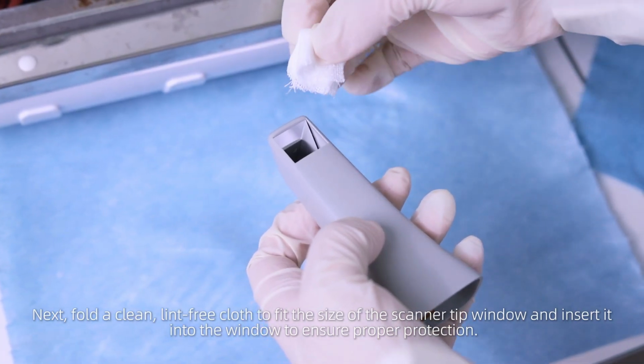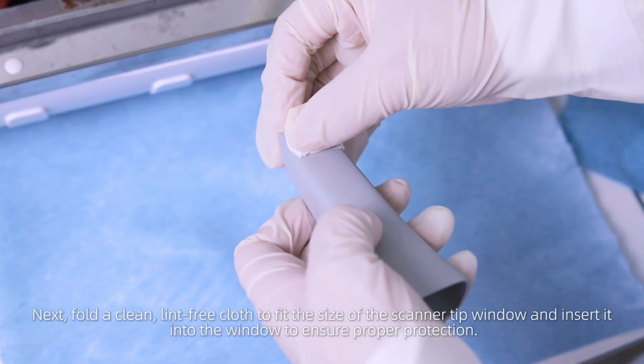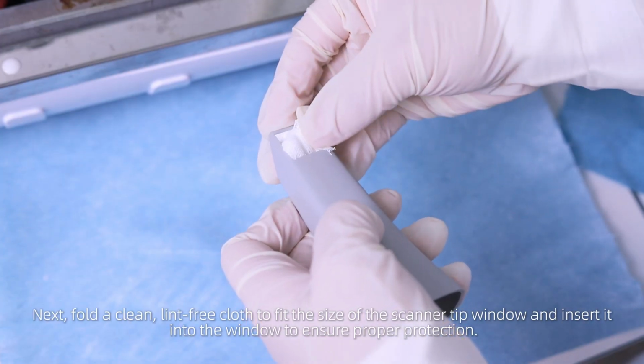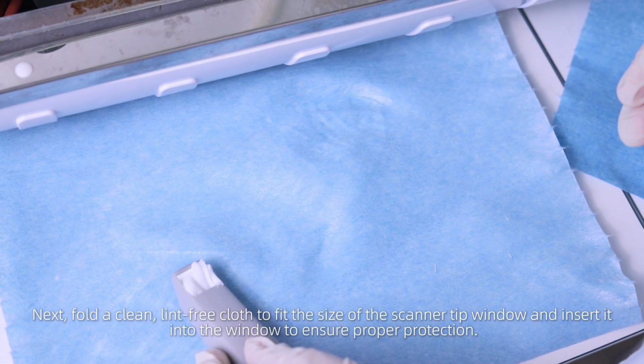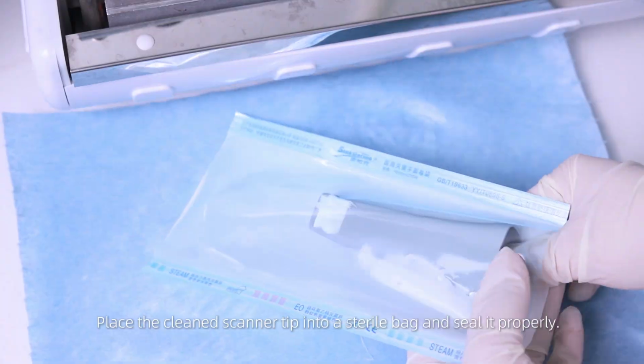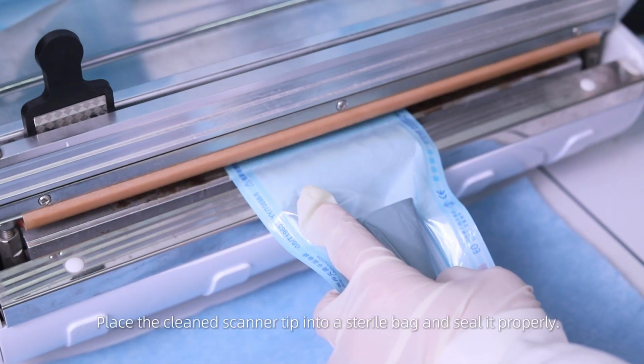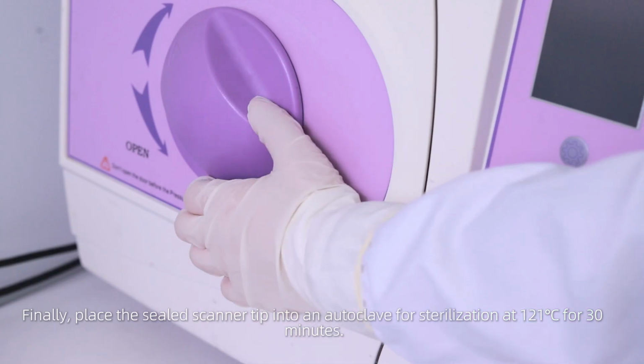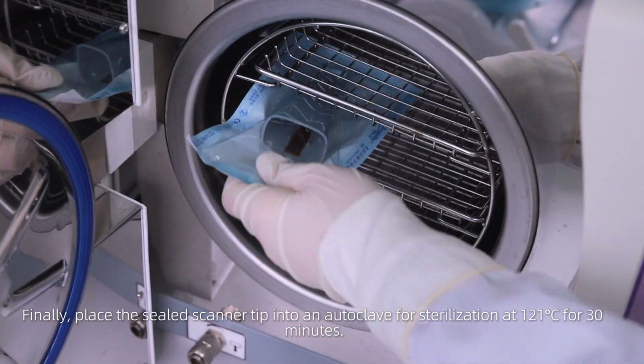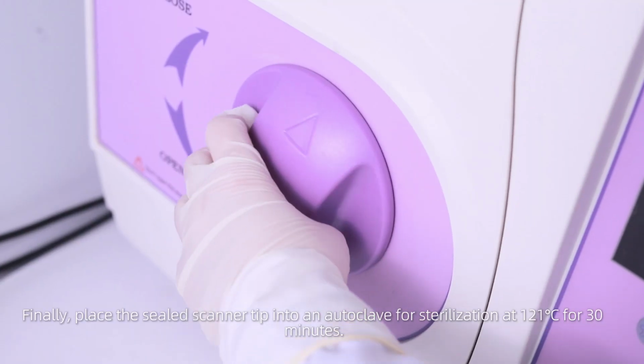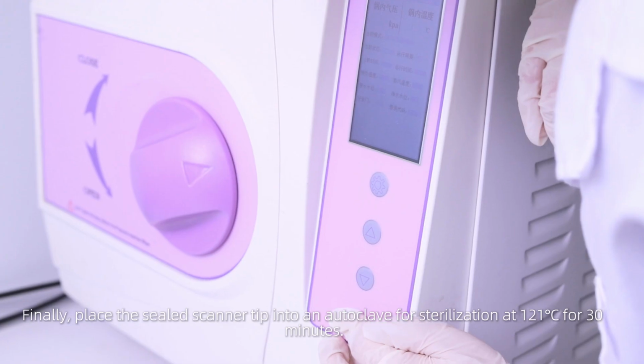Next, fold a clean, lint-free cloth to fit the size of the scanner tip window and insert it into the window to ensure proper protection. Place the cleaned scanner tip into a sterile bag and seal it properly. Finally, place the sealed scanner tip into an autoclave for sterilization at 121 degrees Celsius for 30 minutes.